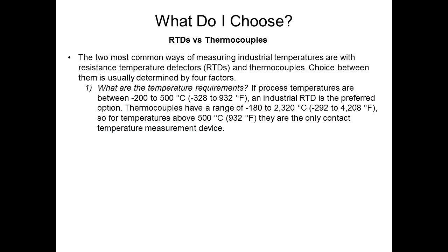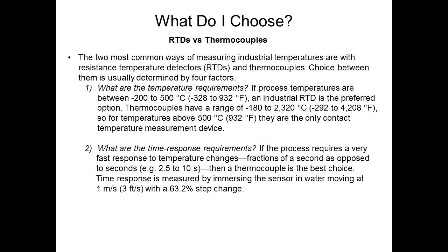So here are some ways to determine which sheaths and probes to select. What are the temperature requirements? If it's, say, minus 200 to 500 C, an industrial RTD is the best way to go for accuracy. If you're going above, say, 800 C or 850 C, you're going to have to go to a thermocouple because RTDs will not operate up there. Speed of response, if that's an issue, fastest is thermocouples. But if you need speed of response and accuracy, maybe a thermistor if it's a low temperature. So there are different ways of measuring these things. These are some of the ways we measure them.